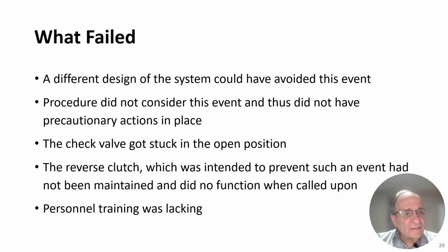It actually failed. A different design of the system could have avoided this event. That's item number 1. The procedure did not consider this event. That's layer number 2. That was a failure in planning, and thus did not have precautionary actions in place. The check valve that got stuck in the open position, that's what failed open. There was a reverse clutch on this turbine that would not allow it to spin in reverse. But for many years it had never operated and the maintenance on it was lacking. Well, this clutch was intended to prevent this very accident from happening. If the turbine ever tried to go in reverse, it would lock the turbine in position and not allow it to spin in reverse. But that failed to kick in when the turbine spun in reverse.